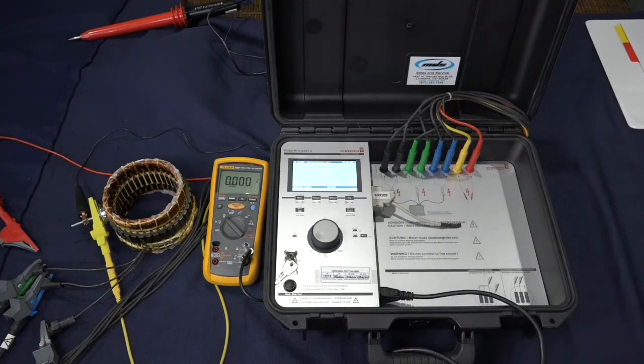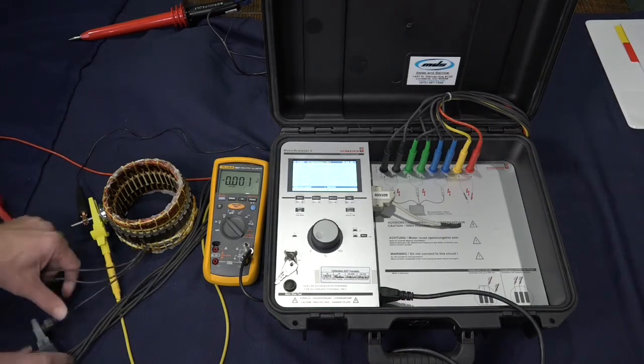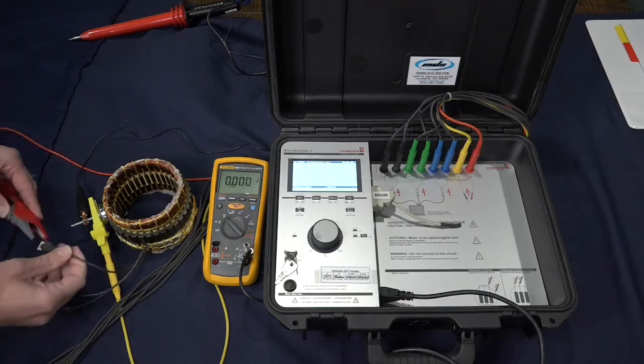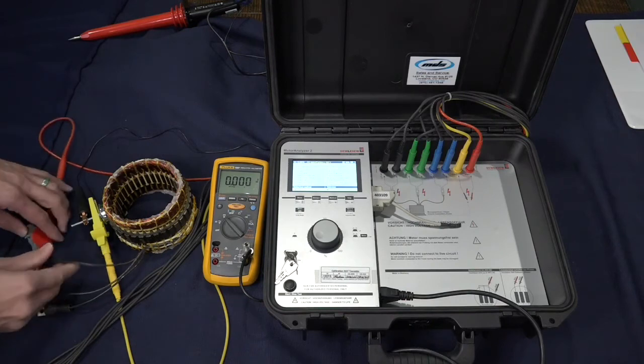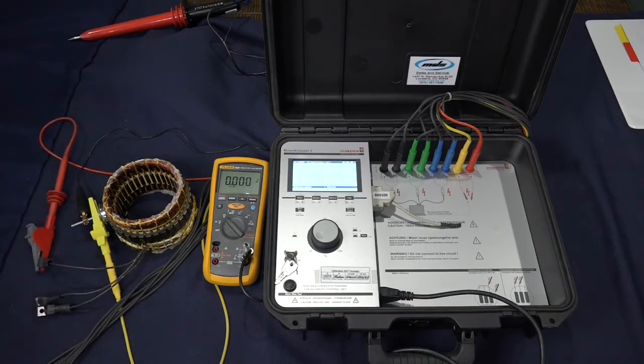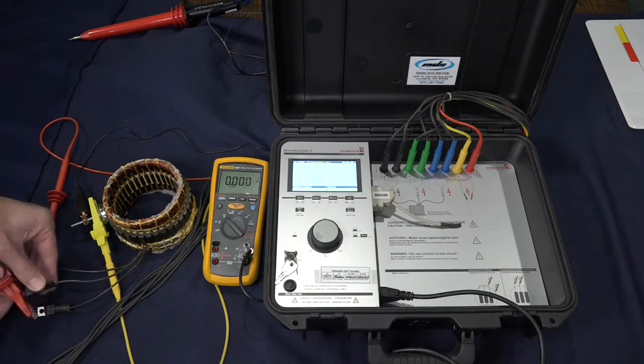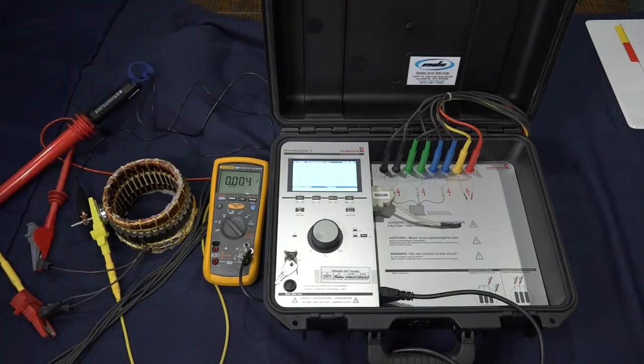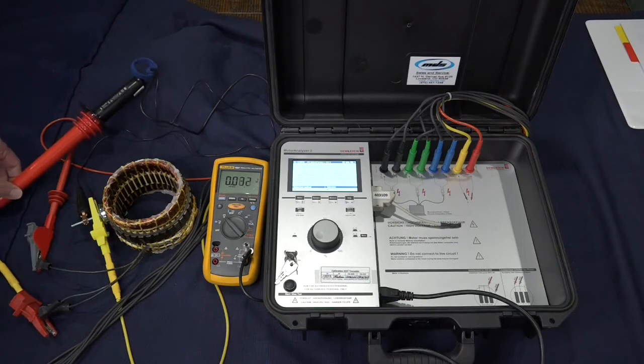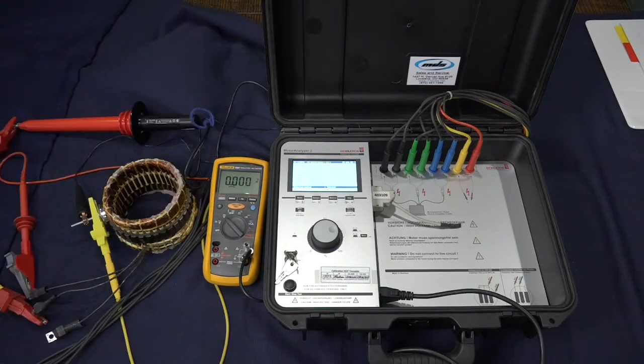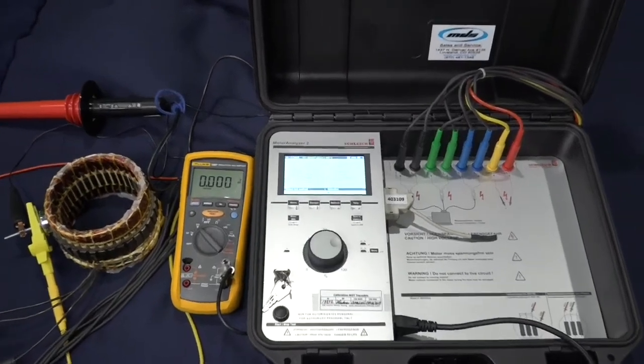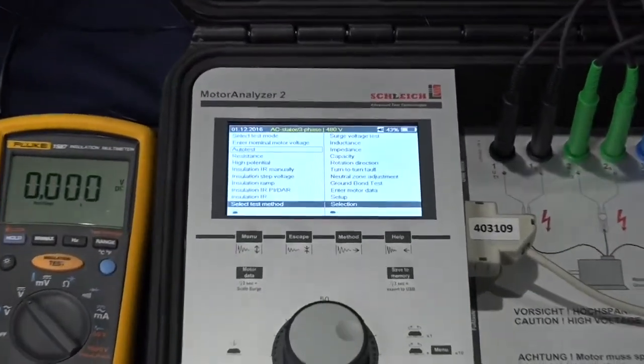So on the stator, what we'll do first is disconnect our normal 3-phase matrix test leads, and we'll disconnect our single high voltage red lead here. Now, as a demonstration that we're actually getting the voltage, I'm going to set up a voltage divider here, and we'll look at the voltage over here. Now that we have our high voltage test lead connected, as you see there on the left, let's zoom in on the screen and I'll show you what I'm doing to select this extra high voltage lead.